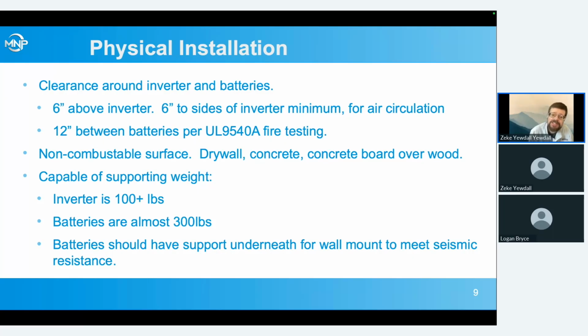Some jurisdictions are sticking to 36 inches between each battery, which is kind of the default in the NFPA 855 battery code. If you don't have the fire testing, it is supposed to be overridden by the manufacturer's results of the fire testing, which says 12 inches in our manual, but not all jurisdictions are accepting that. LA Fire Department is one I've heard is not doing that. So you may have to have more clearance for reasons like that.